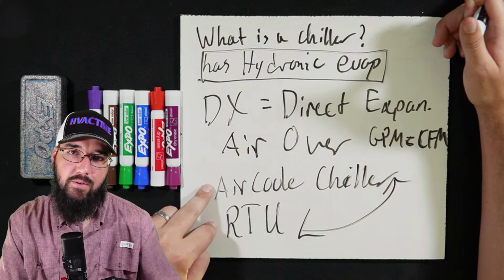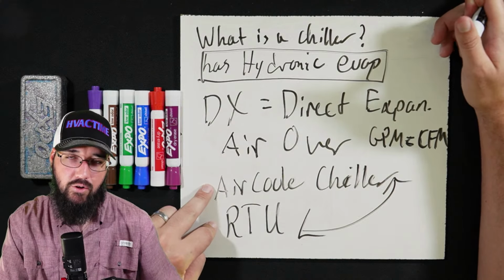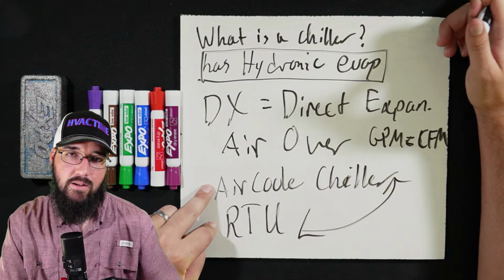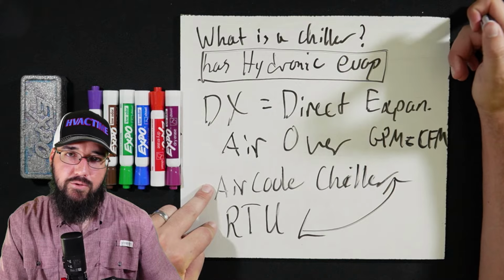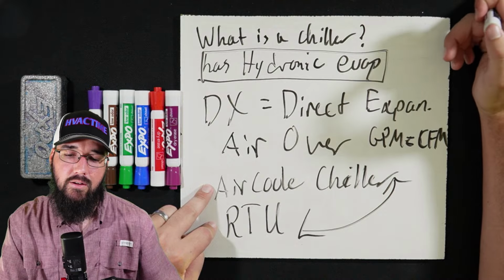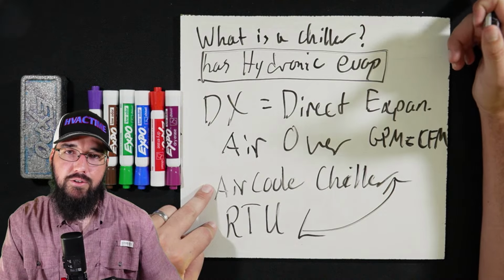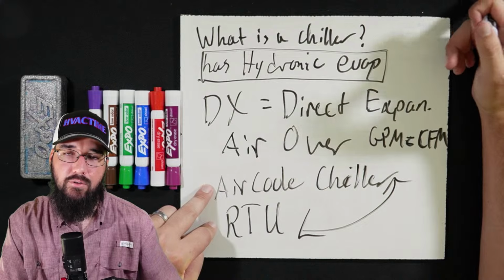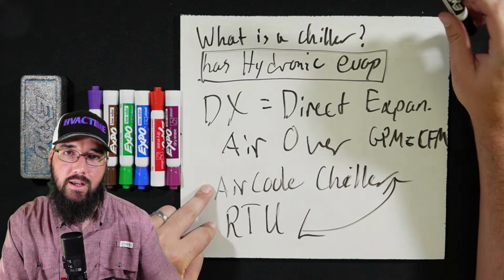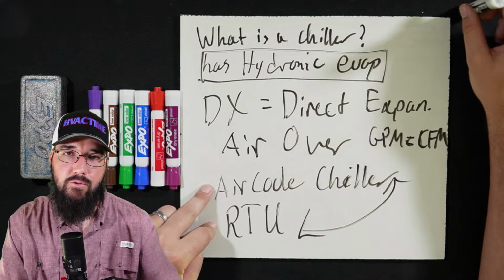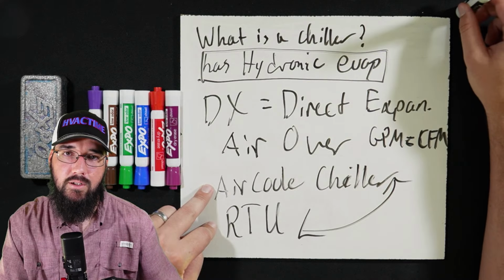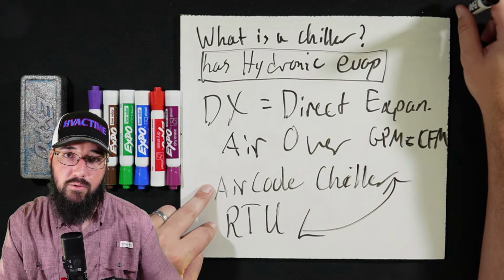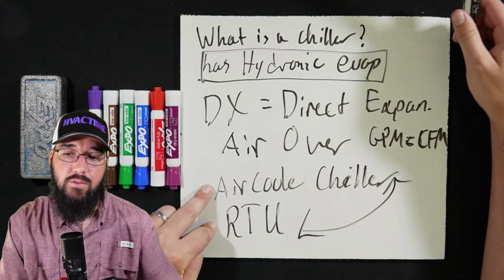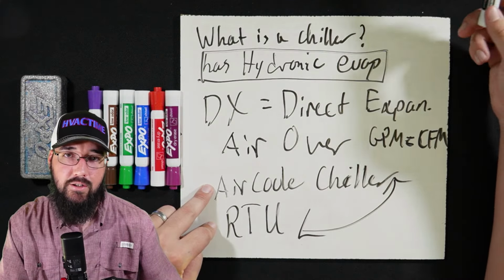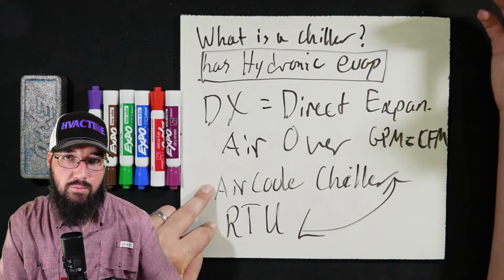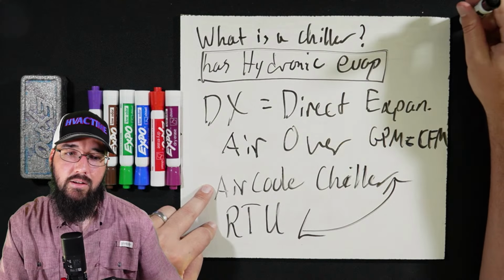Really take some time to think about these. I encourage you to try to do that. How would you troubleshoot a low pressure issue on an RTU? What's one of the first places you would go to look at if your evaporator was tripping on low suction pressure? Me? I'm going to go check the blower motor. Did it throw a belt? Is the fan spinning? Did trash get into the fan? What's my static pressure I'm running at? That's what I want to see.